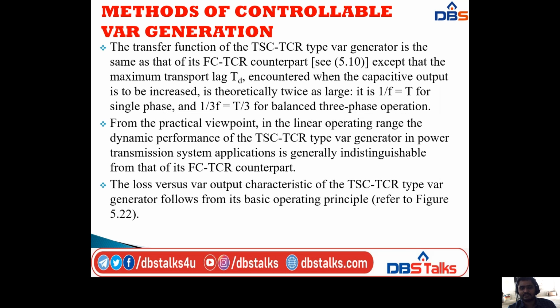Next, the transfer function of the TSC-TCR VAR generator is the same as that of its FC-TCR counterpart. This FC-TCR counterpart is the previous concept. This is one of the methods of controllable VAR generation, except that the maximum transfer delay, encountered when the capacitor output is to be increased, is theoretically twice as large.